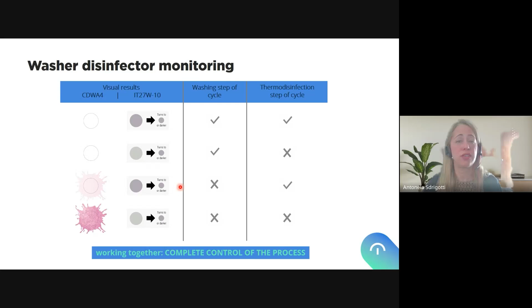So we have finished the monitoring, because we were talking here about the activity. We're monitoring the processes, the process parameters. But now we are going to verify. And how are we going to verify? By measuring and evaluating residual contaminants after the cleaning process. Traditionally, and we will not do this on a daily or cycle basis, okay? So how do we make sure that actually the result is a totally clean instrument?